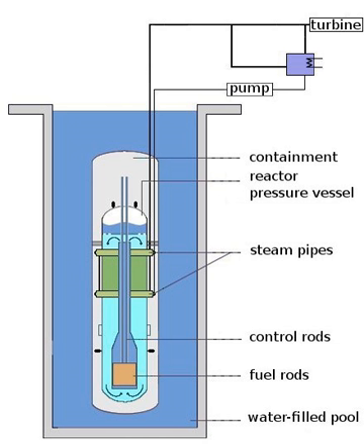In boiling water reactors, the fuel is similar to PWR fuel except that the bundles are canned — that is, there is a thin tube surrounding each bundle. This is primarily done to prevent local density variations from affecting the neutronics and thermal hydraulics of the nuclear core on a global scale. In modern BWR fuel bundles, there are either 91, 92, or 96 fuel rods per assembly depending on the manufacturer. A range between 368 assemblies for the smallest and 800 assemblies for the largest US BWR forms the reactor core, and each BWR fuel rod is back-filled with helium to a pressure of about 3 atm.